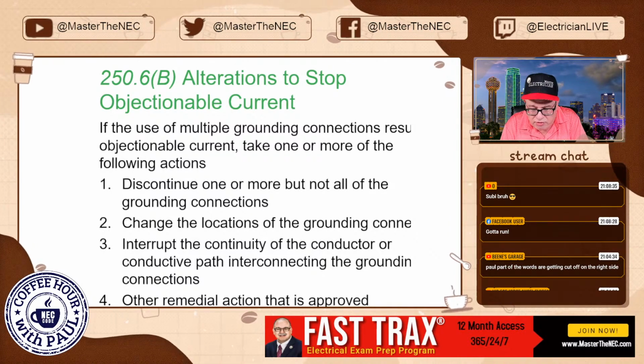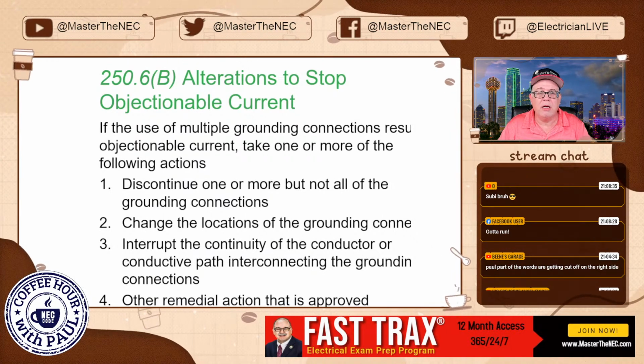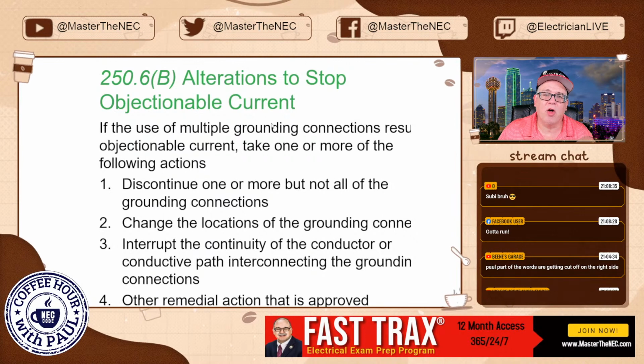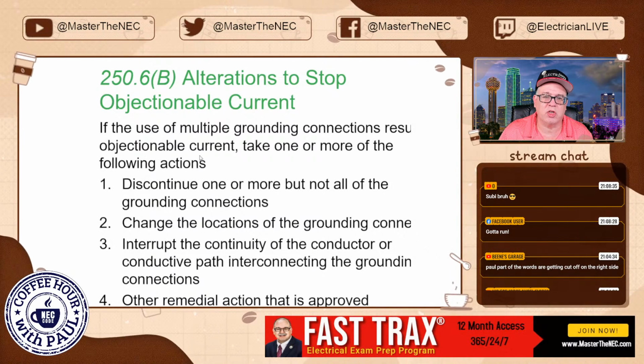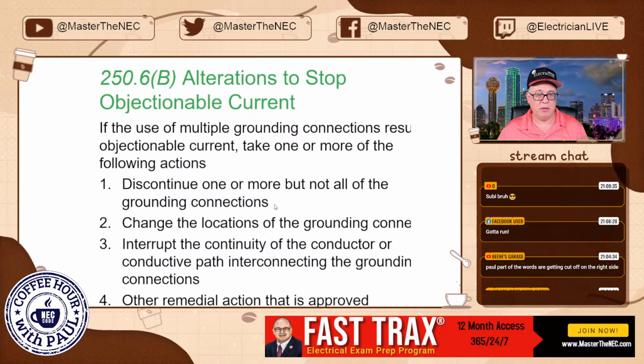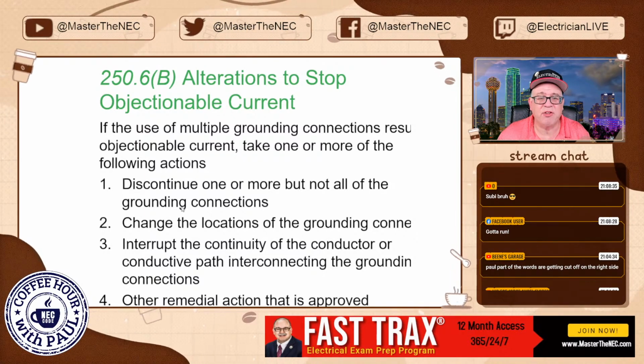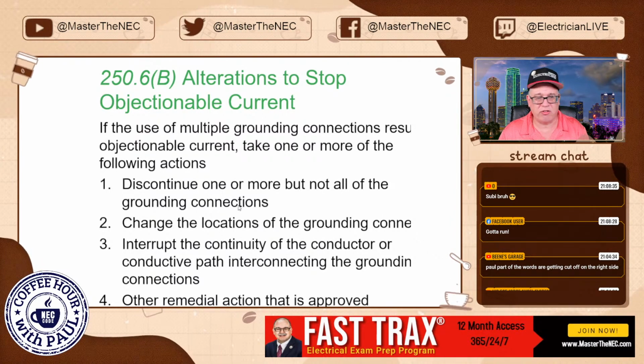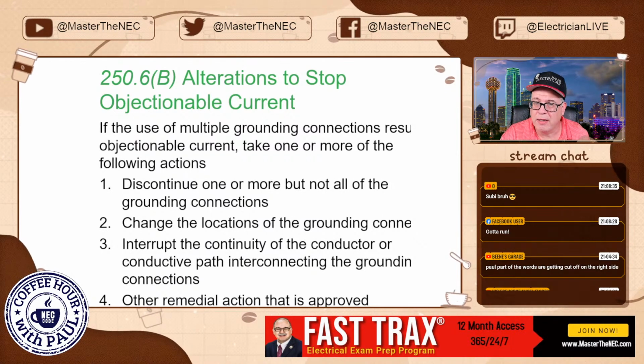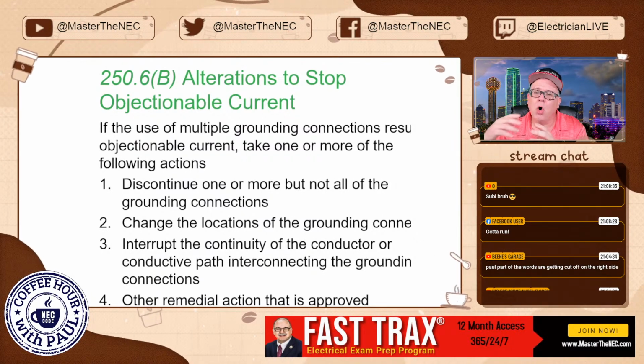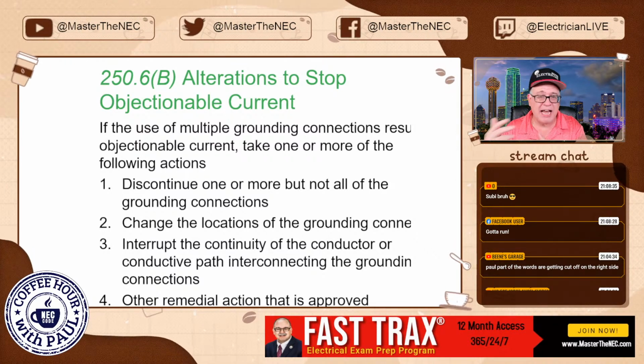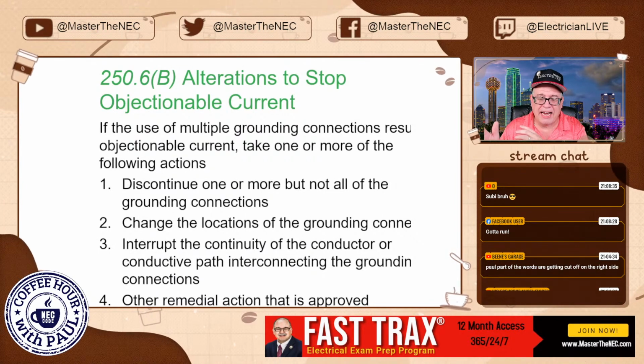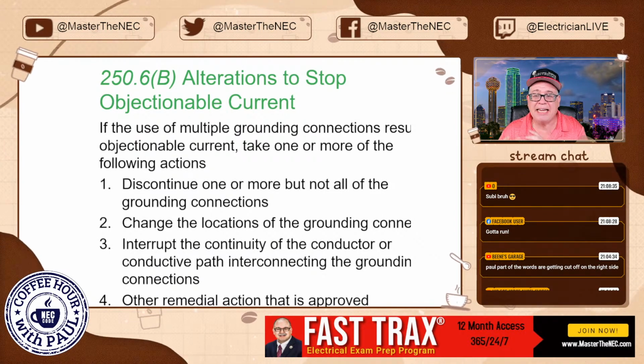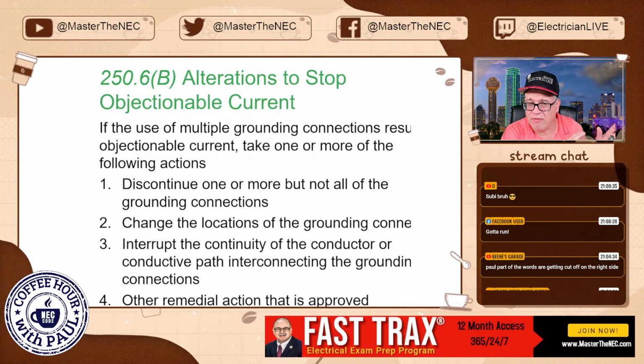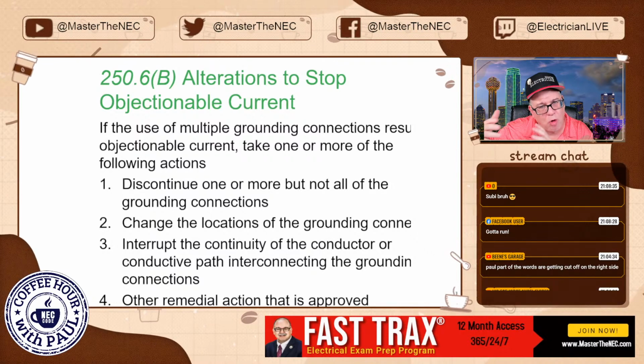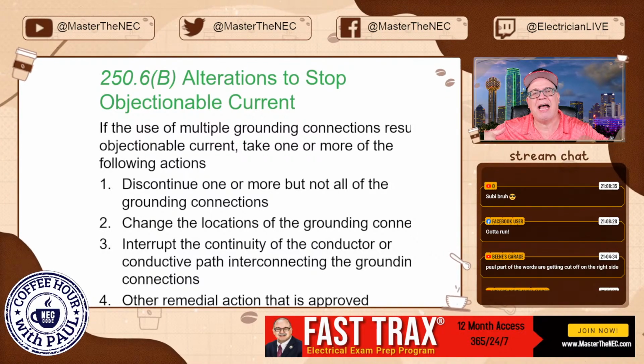So let's say you have an objectionable current condition, maybe one that we just saw. What do you got to do? Well, if the use of multiple grounding connections results in objectionable currents, take one or more of the following actions. Well, I have to analyze what's being done, and I have to disconnect one or more, but not all of the grounding connections. I don't want to lose the integrity of the service, but I might have to look at what goes downstream. What did I do that created my condition? I will start to look at it and maybe move things around. Now, I cannot get rid of my intended path at the service, but I might want to see what I did wrong downstream and start looking at how I fix this.